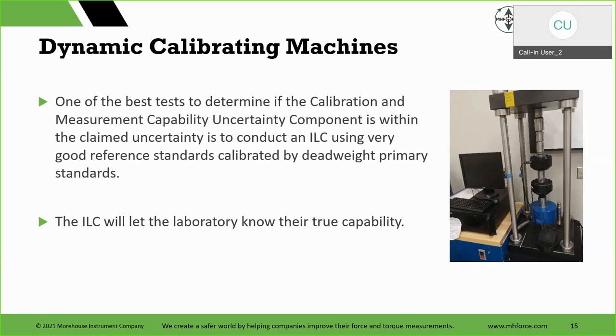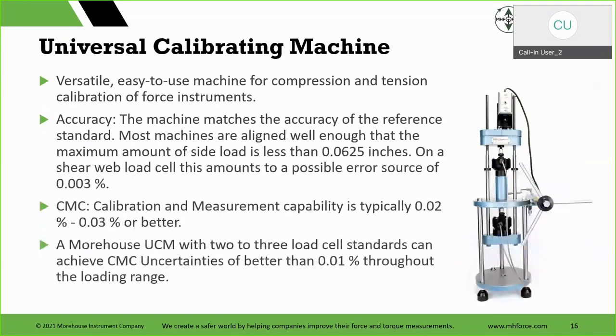The proficiency tests on the market today are not as good as taking two standards calibrated with deadweight, which is called dissemination error, putting them together and seeing what the difference is. That's gonna really tell you if you're in with your claimed uncertainty or not. So then we get to the universal cal machine.